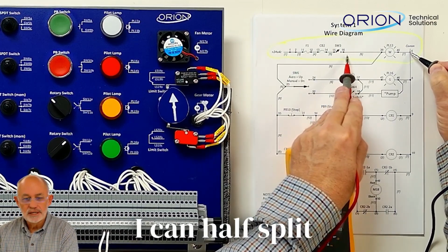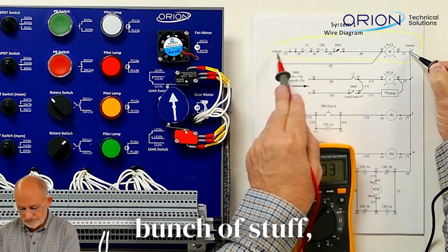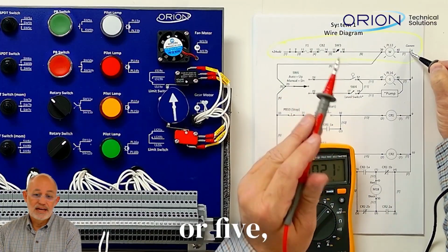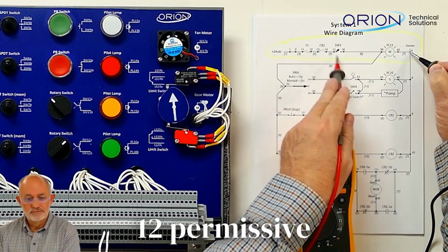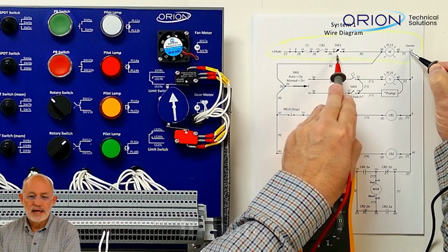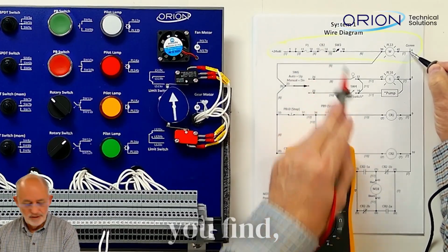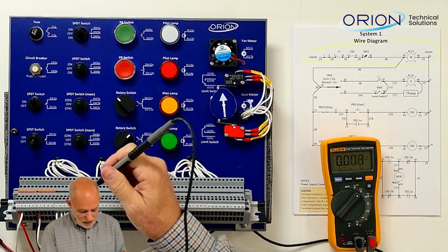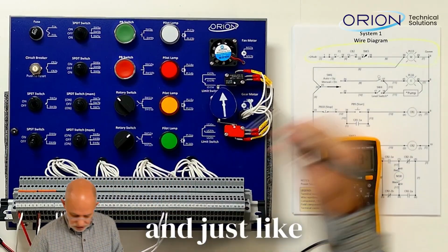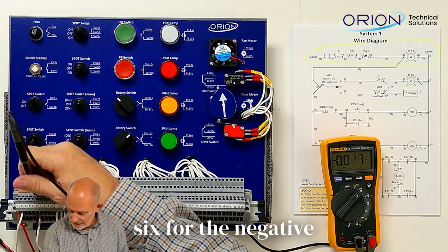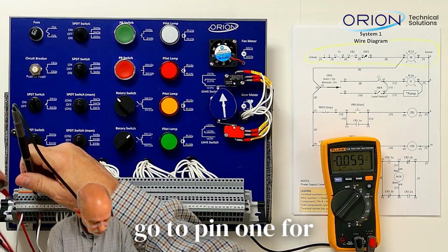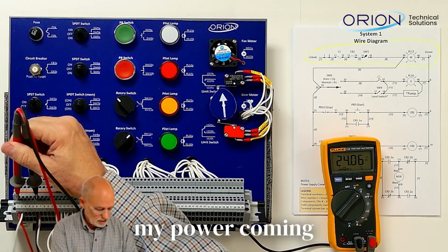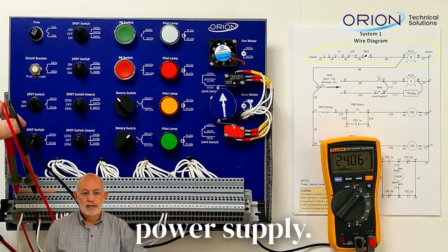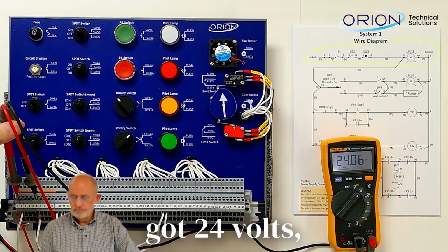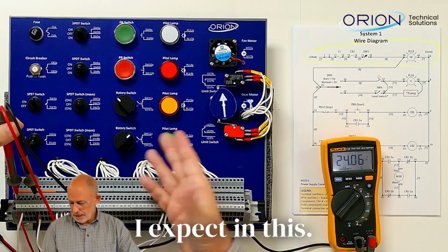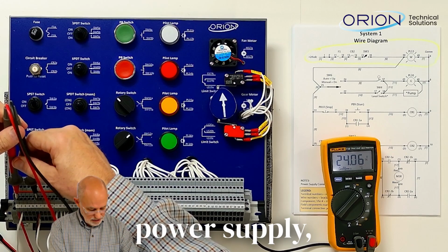I can half split if there's a whole bunch of stuff, like some systems where you'll have 4, 5, 8, 10, 12 permissive switches and so forth. Maybe cut that in half and then, based on what you find, go either direction. But in this case, I'm going to go to 6 for the negative, and then I'm going to go to pin 1 for the positive, which is just my power coming right from my power supply. And so it looks like I've got 24 volts, which is what I expect in this. It's a 24 volt power supply, so we're good.